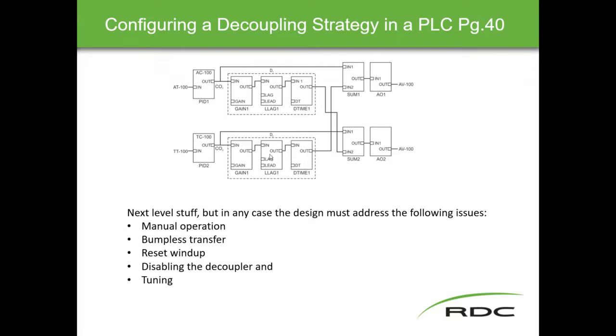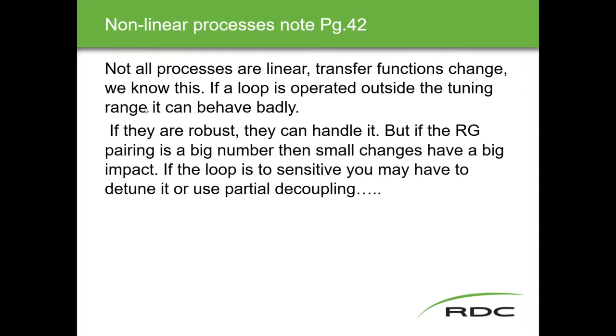Other design provisions include disabling the decoupler — turning it on and off, usually combined with the auto/manual setup — and tuning values calculated and put into the blocks. On non-linear processes: we talk about things theoretically being linear because it's easier, but very few processes actually are. Transfer functions change. A loop operated outside its tuning range can behave badly, which is why we always tune at the output level we'll typically be running at. If the relative gain pairing is a big number, small changes will have a big impact.